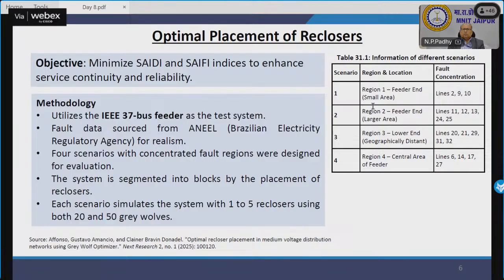So now, how do we do the optimal utilization or placement of reclosers? The objective is to minimize SAIDI and SAIFI indices to enhance service continuity and reliability. The methodology utilizes the IEEE 37 bus feeder as the test system, with fault data sourced from ANEEL, the Brazilian Electricity Regulatory Agency, for realism.